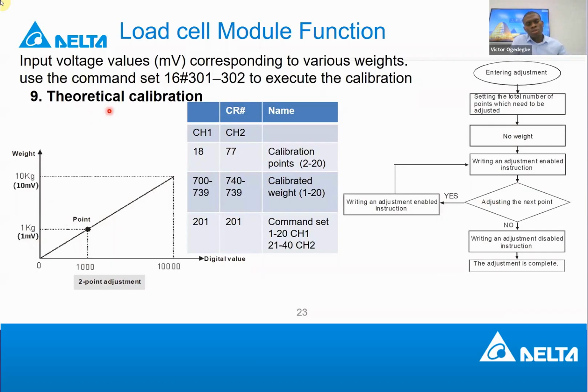You are just assuming that if I measure this millivolts from the sensor, I want to have this digital value that is being calibrated. I think for this, there should be a control register for the theoretical voltage. But for this register, this is where you specify the digital value that you want. For example, 1000: you write 1000 here because when it measures 1 millivolt, there should be 1000. Also in the load cell module, the load cell wizard, you can do that. So this is the flow. It's just the same as what we saw before.